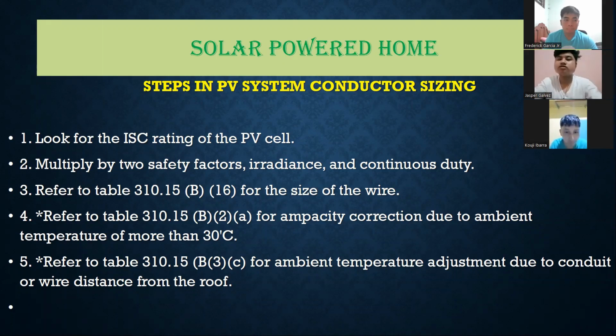So first step is look for the ISC rating of the PV cell. Second step is multiply by 2 safety factors, which is irradiance and the continuous duty. Step 3, refer to the table 310.15(B)(16) for the size of the wire. Step 4, refer to table 310.15(B)(2)(a) for ampacity correction due to ambient temperature of more than 30 degrees Celsius.